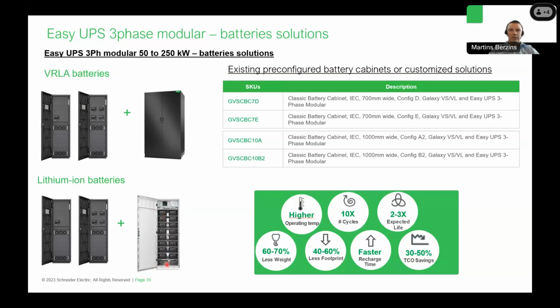And this lithium-ion cabinet is 650 millimeters wide, and the weight of this cabinet is 470 kilograms. If we compare a similar solution with lead acid batteries, to have 30 minutes for 50 kilowatts, you would need to use this battery solution I'm pointing out. So it's a classical battery cabinet, which is 1 meter wide.